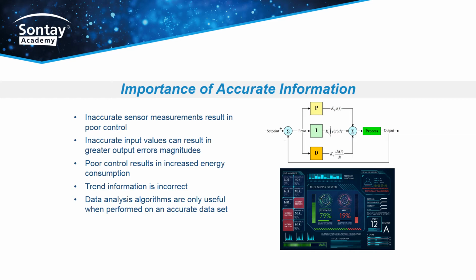Trend information is incorrect, and data analysis algorithms are only useful when performed on an accurate data set. The purpose of a controller is to eliminate any difference between a set point and a measured value. If the value that you are feeding into a control process is not accurate, then the result that you will generate when trying to eliminate the control difference will also be inaccurate. The result output may be many times greater, as is shown in the example on the following slide.